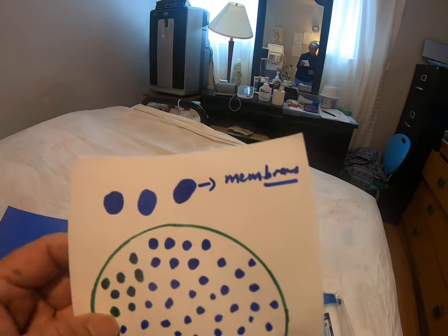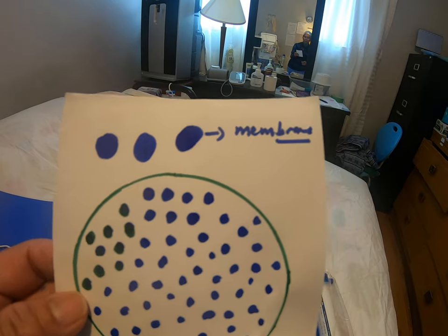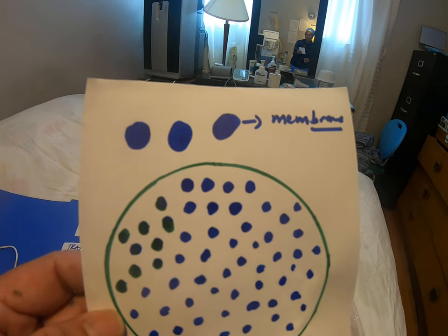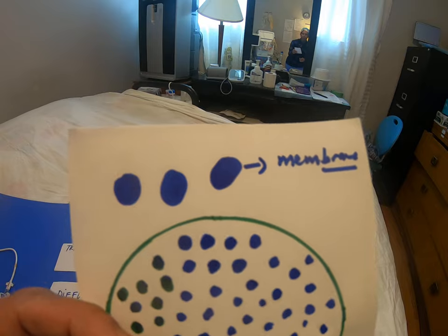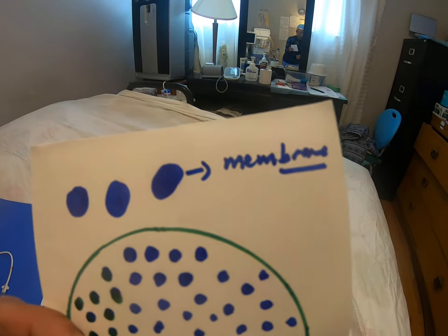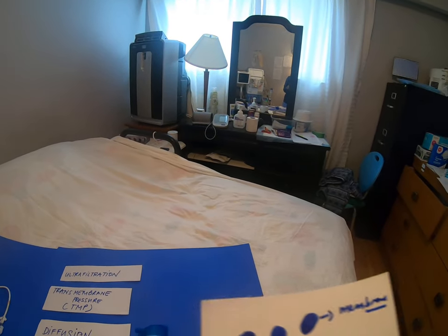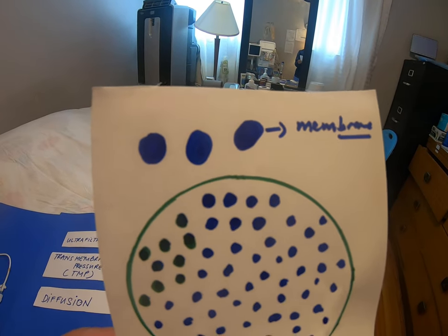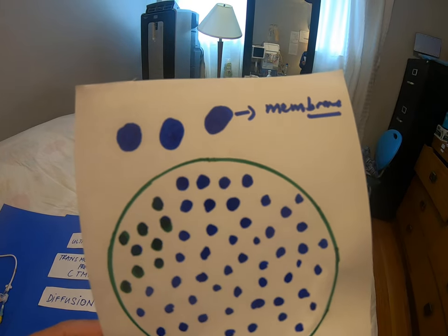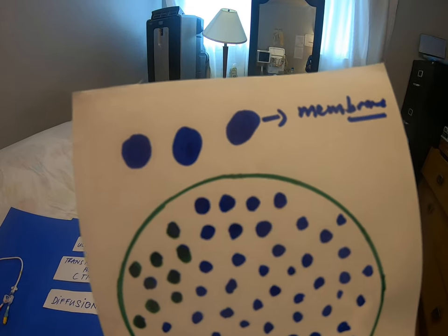Around each fiber we have a membrane. Inside the fiber is where blood flows. So blood is inside each fiber, and outside the fiber is our dialysate. The blood and the dialysate are separated by that membrane. The inside of the fiber — where blood is — has positive pressure, and outside the fiber the dialysate has negative pressure.